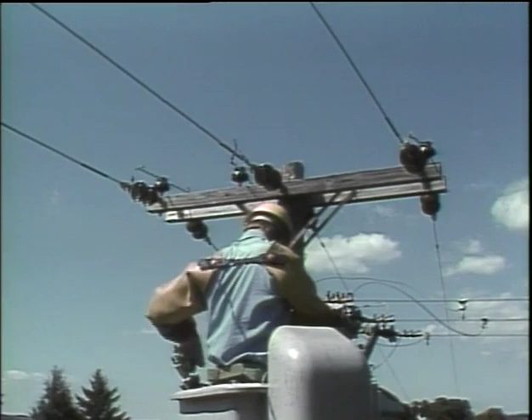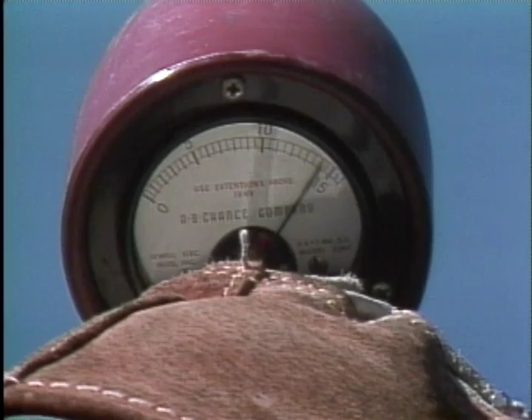Another way to test the circuit with a phasing test set is to place the hooks on two phase lines. This method is used to check for the presence of phase-to-phase voltage. This voltage reading indicates the circuit is live. As with the other testers, the phasing test set should be checked on a live source after it's used.